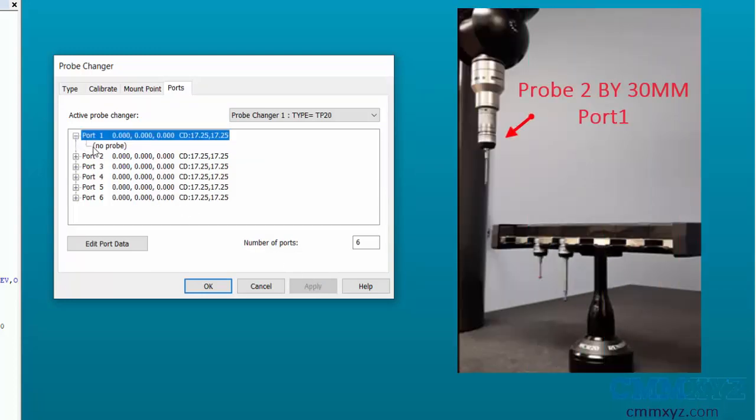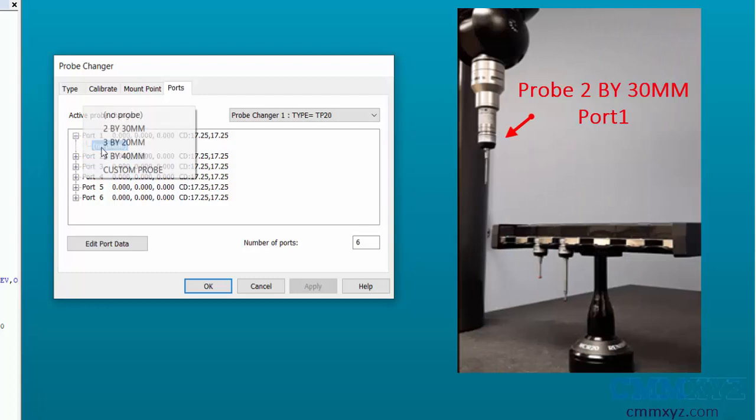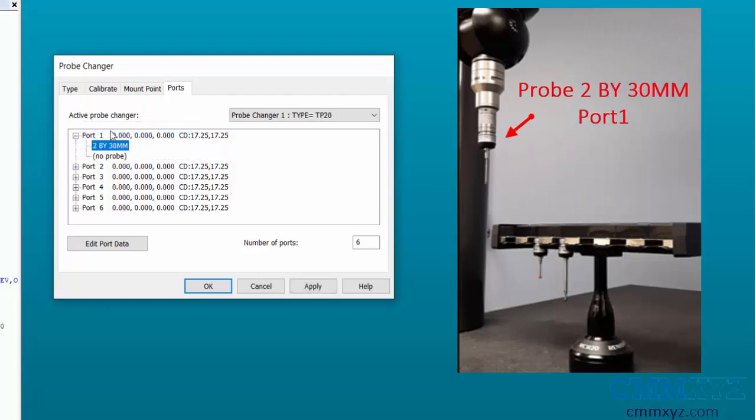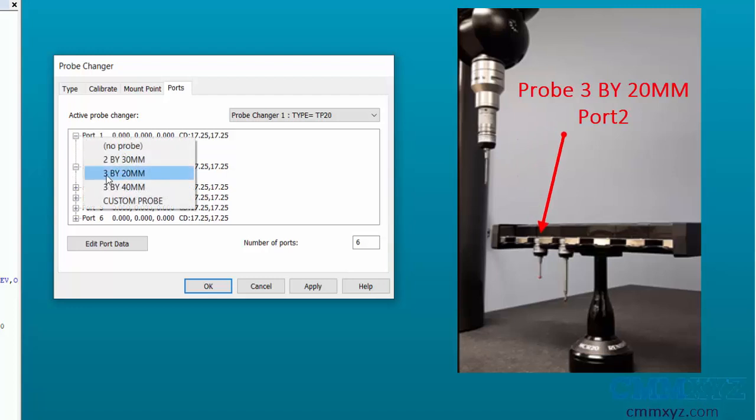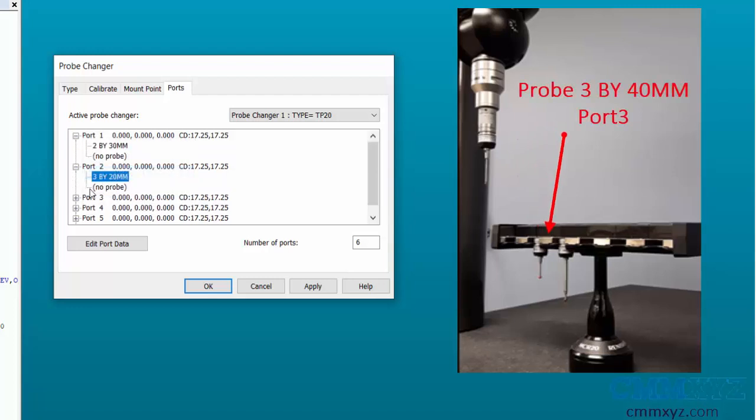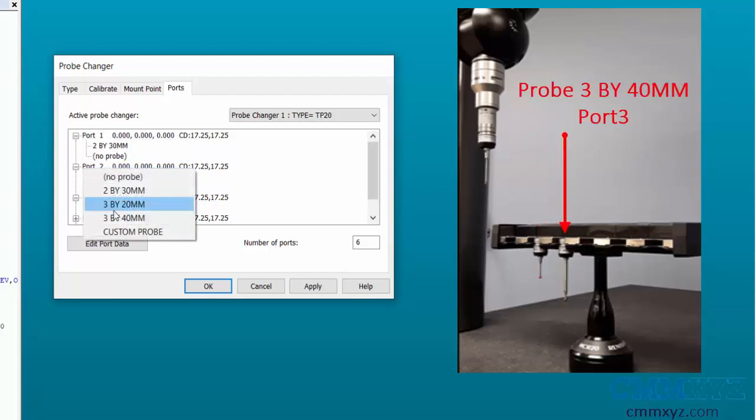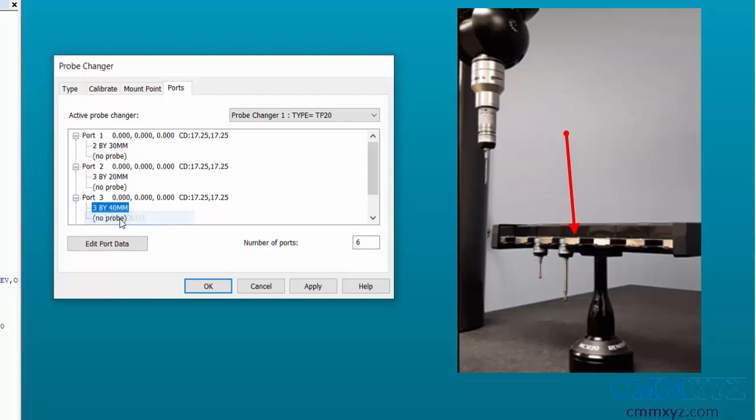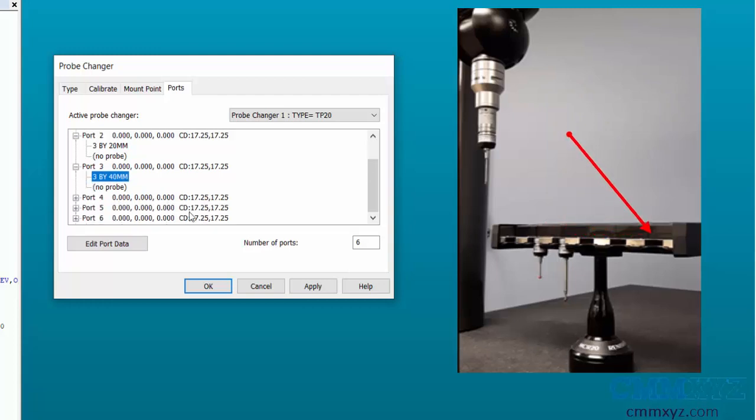Next, add the modules to their respective ports according to your setup on the CMM. I have probe 2 by 30 millimeters in port 1, probe 3 by 20 millimeters in port 2, and probe 3 by 40 millimeters in port 3. Leave the rest of the ports empty and apply the changes.